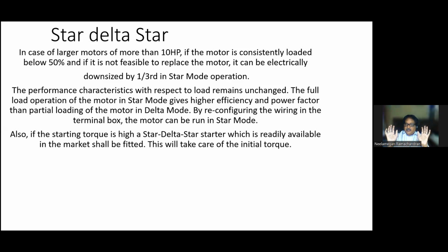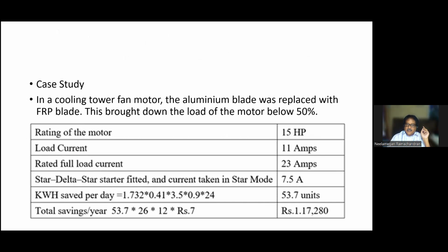So what we did is we just changed the starter into a star-delta starter. So this was the saving. 15 HP, load current 11 amp, full load current 23, it was taking 7.5, units saved is 53, 1 lakh. By just electrically downsizing the motor, we were able to gain this.